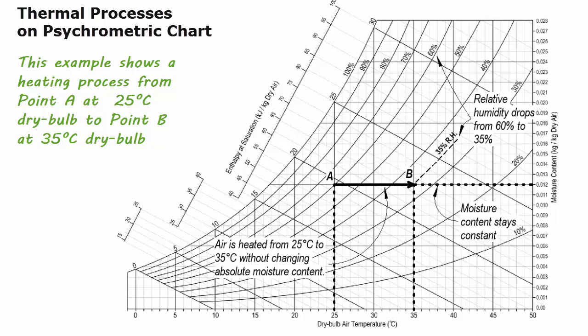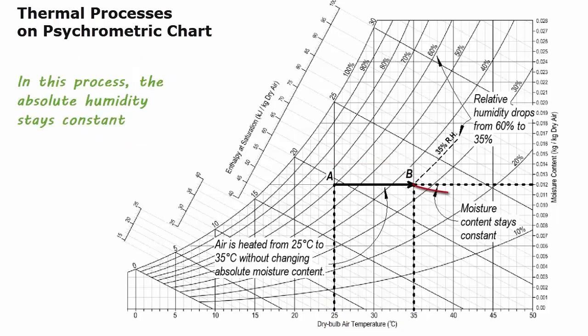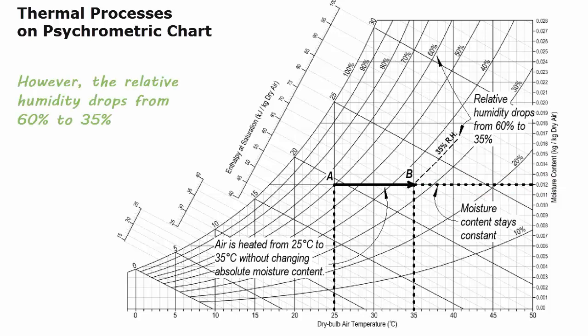This example shows a heating process from point A at 25 degrees C dry bulb to point B at 35 degrees C dry bulb. In this process, the absolute humidity stays constant. However, the relative humidity drops from 60% to 35%.